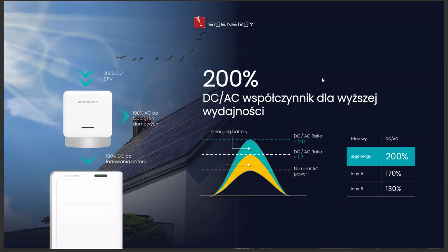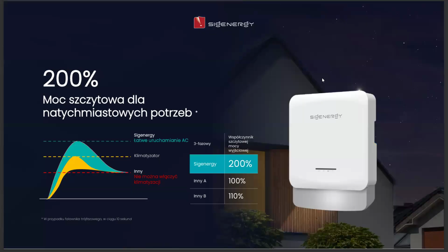At the same time, 100% of the inverter rated power can be exported directly to the grid, while the additional 100% can charge the energy storage system simultaneously, without additional conversion losses. Slide 17. Backup power, inrush current under control. Another key advantage is 200% peak power in backup mode. The inverter can handle 2x overload for up to 10 seconds.